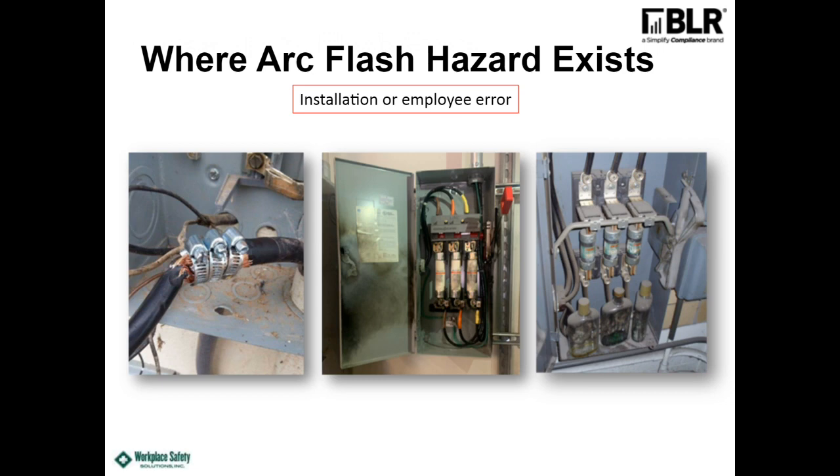On the right, this is just bad practice, it's having storage. This was a distillery, and you can probably tell that, but it's not a good place to store stuff. You don't store things in an electrical panel, and that's just asking for accidents.